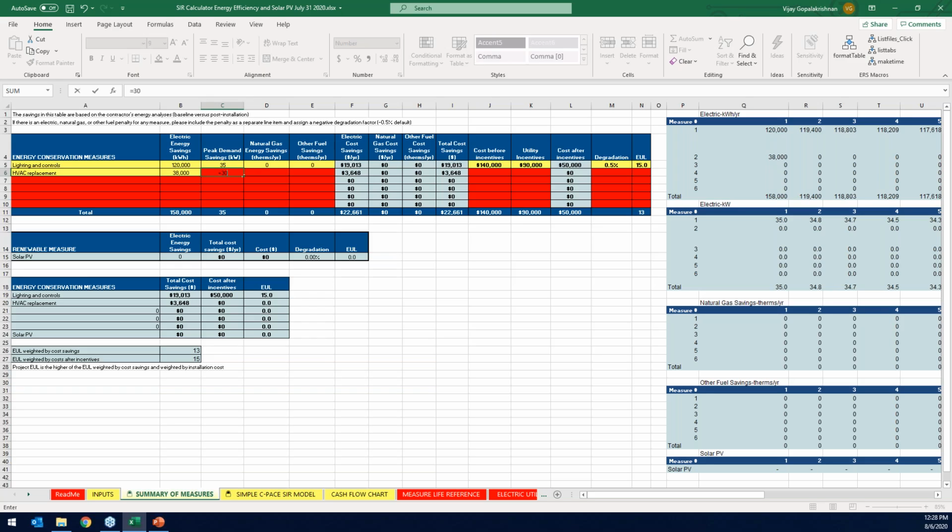So we would put the 30 multiplied by the 4 months divided by 12 months, because all the calculations occur in terms of annual demand savings. The cost savings are in terms of 12 months, so you need to make sure you scale this down to match the average over 12 months rather than just the peak of the 4 months where the savings are realized.